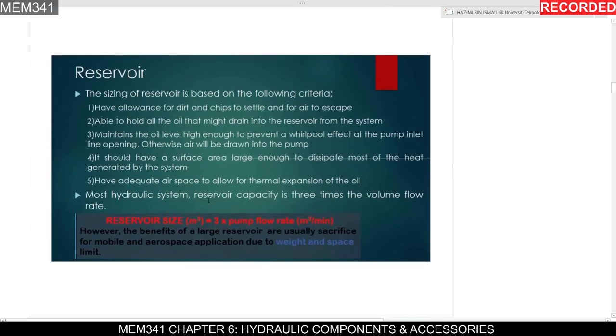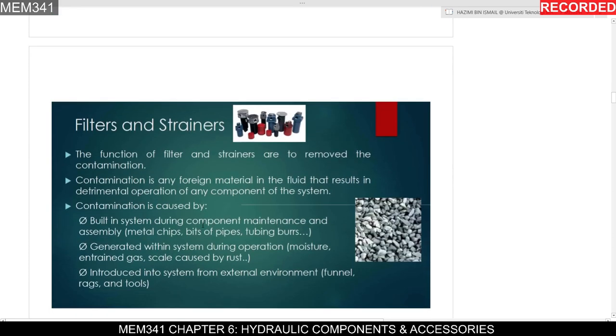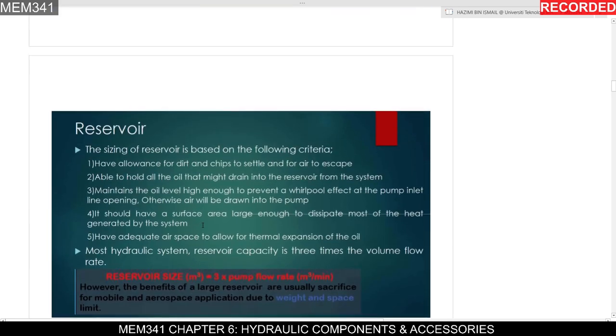How do we determine the proper reservoir size? The rule of thumb is that the size of the reservoir is 3 times larger than the pump flow rate. So you have to know the value of the pump flow rate, multiply it by 3, and then you will get the size of the reservoir. That's all for the reservoir.